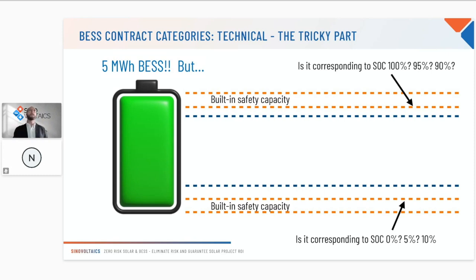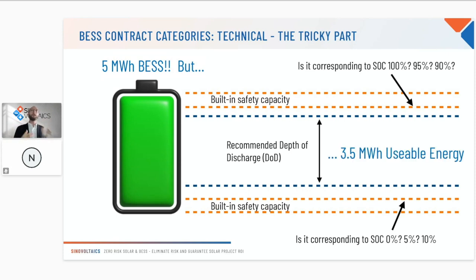And within that available energy, you have to be careful about the recommended depth of discharge, because you might have access exactly to 0% to 100% SOC, but if you can actually use only 80% to 20%, it's a totally different story. So in the end, what you may end up with is that you are buying a 5 MWh BESS, but you are getting a usable 3.5 MWh BESS.